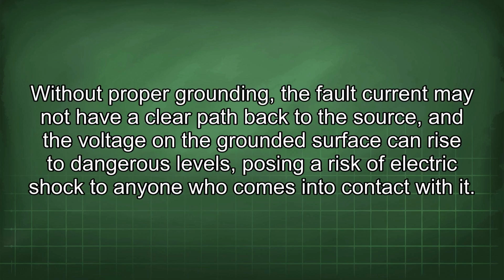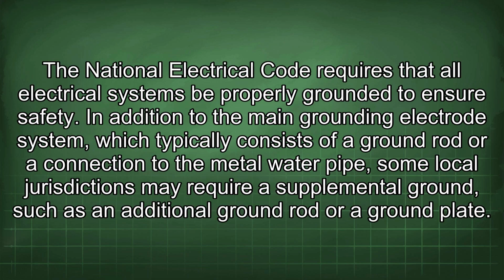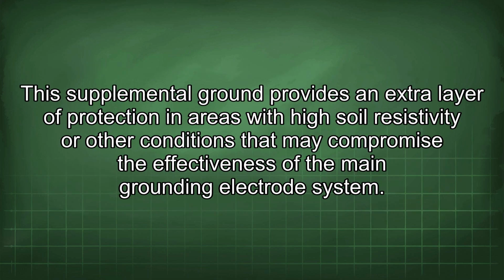Without proper grounding, the fault current may not have a clear path back to the source, and the voltage on the grounded surface can rise to dangerous levels, posing a risk of electric shock to anyone who comes into contact with it. The National Electrical Code requires that all electrical systems be properly grounded to ensure safety. In addition to the main grounding electrode system, which typically consists of a ground rod or a connection to the metal water pipe, some local jurisdictions may require a supplemental ground, such as an additional ground rod or a ground plate. This supplemental ground provides an extra layer of protection in areas with high soil resistivity or other conditions that may compromise the effectiveness of the main grounding electrode system.